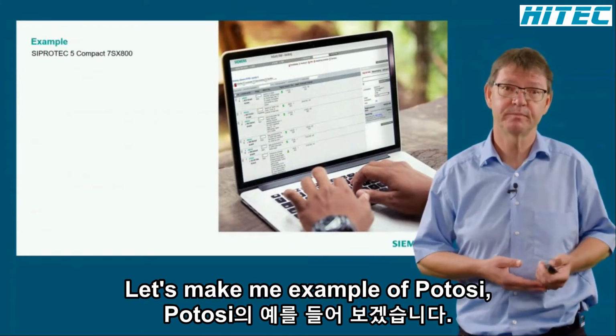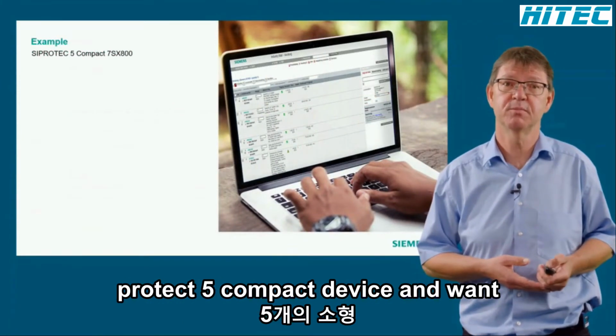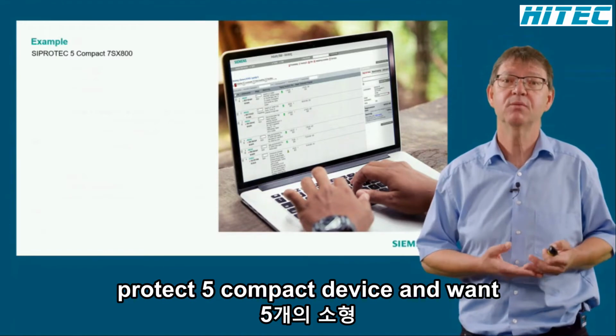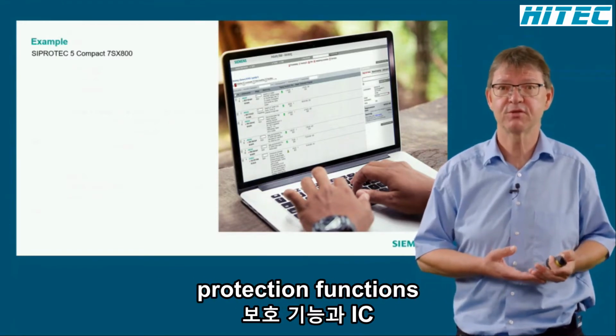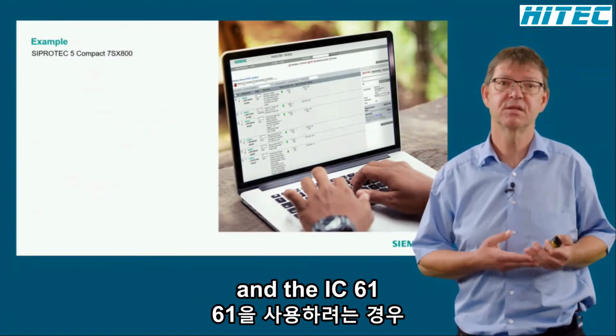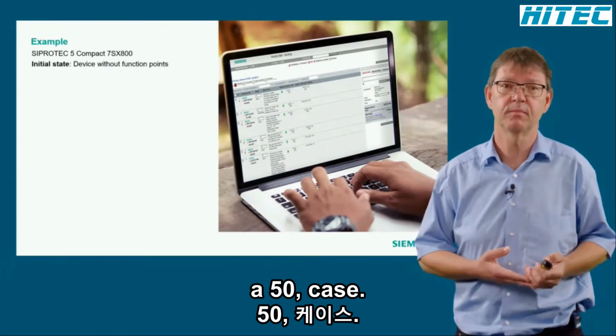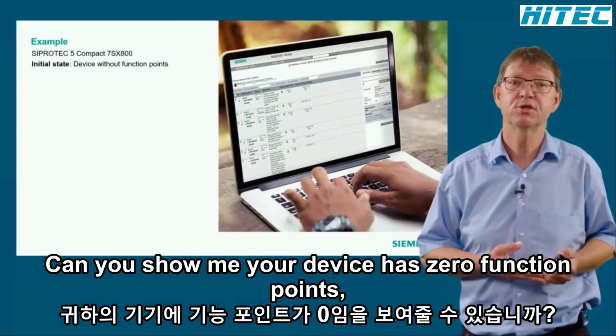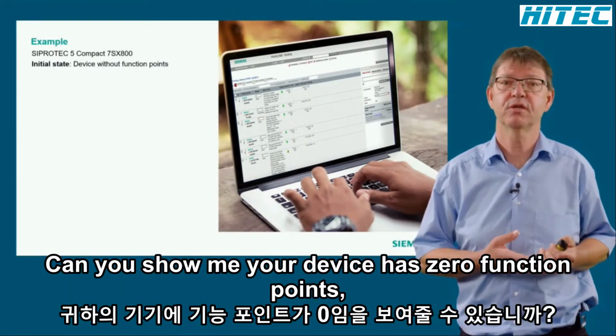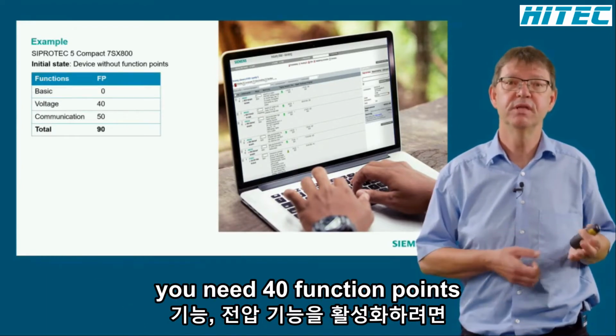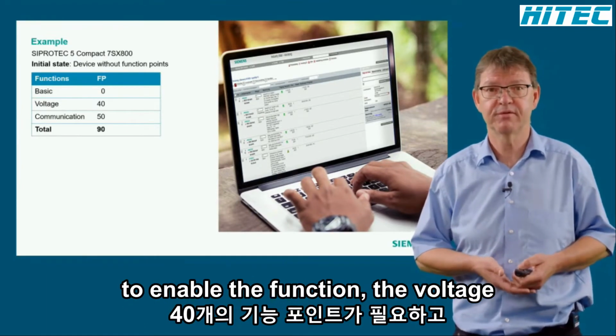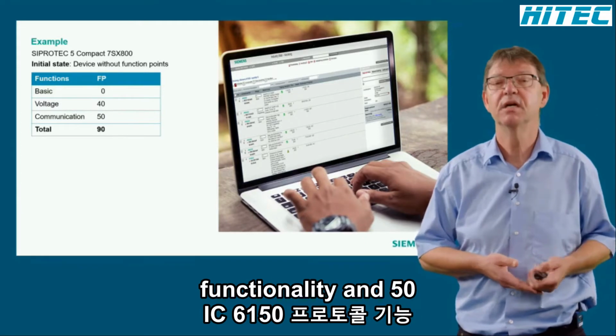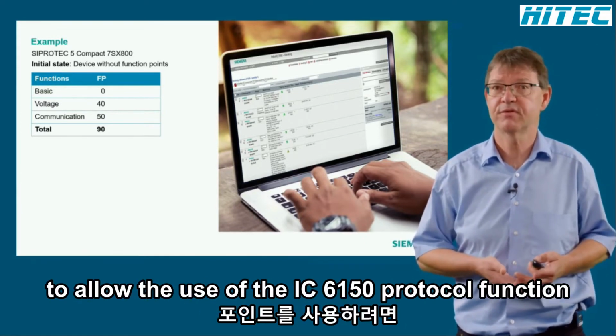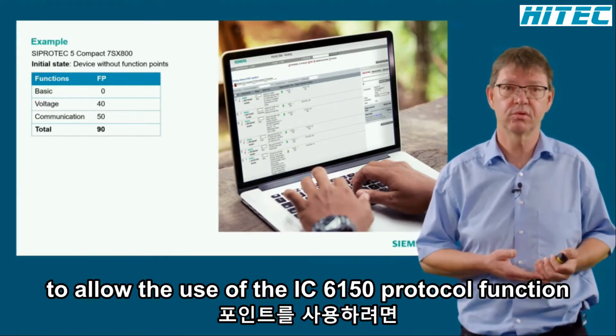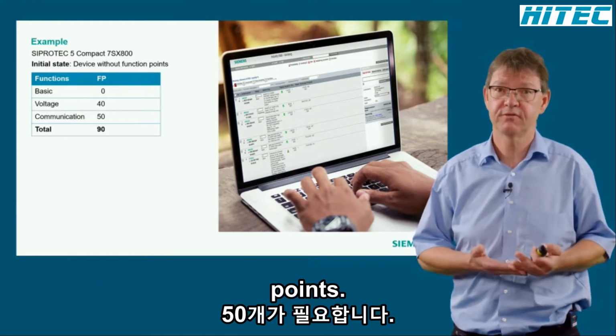Let's make an example. Let's assume you have bought a SIPROTEC 5 compact device and you want to use voltage protection functions and the IEC 61850 communications protocol. Initially, your device has 0 function points. You need 40 function points to enable the voltage functionality and 50 to allow the use of the IEC 61850 protocol. So in total, 90 function points.